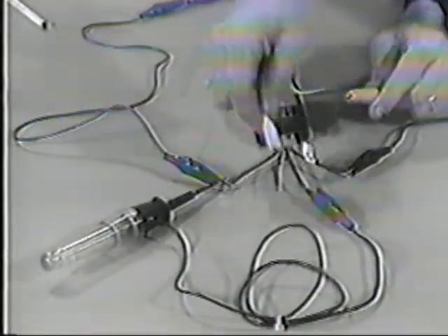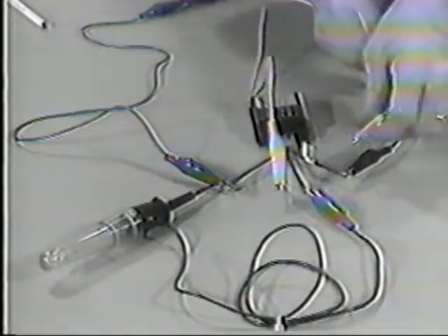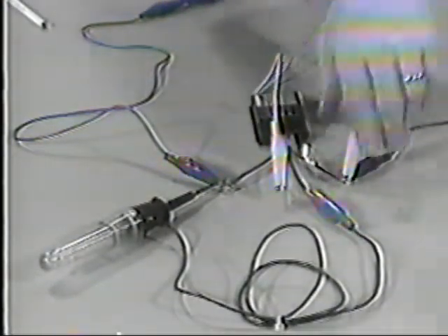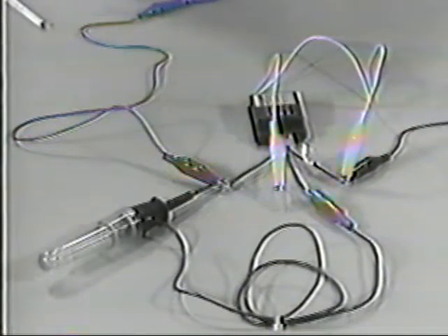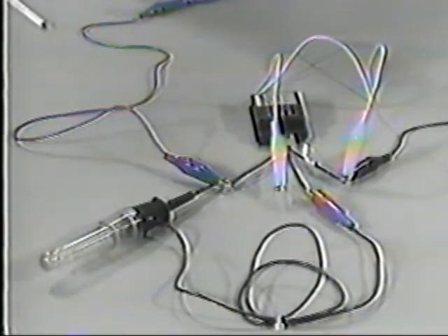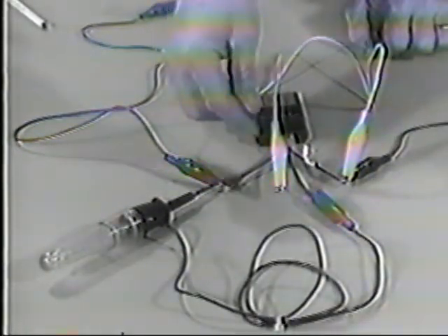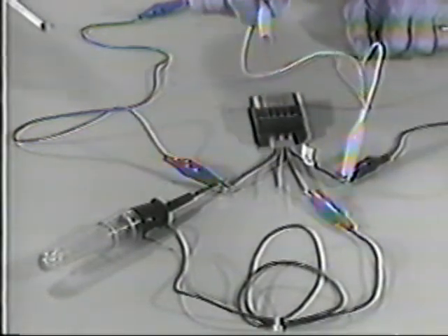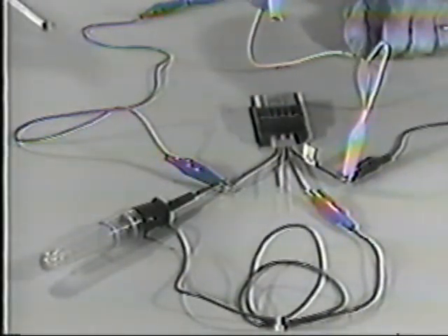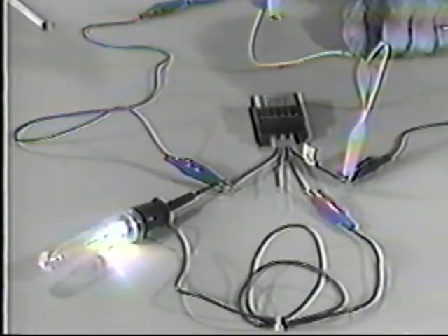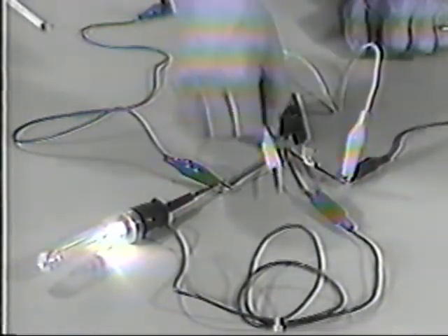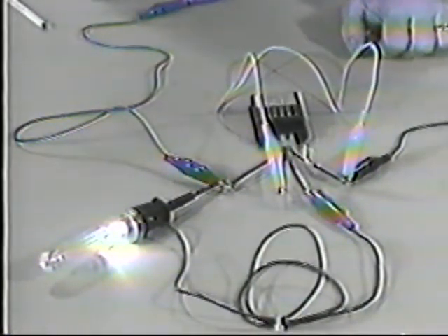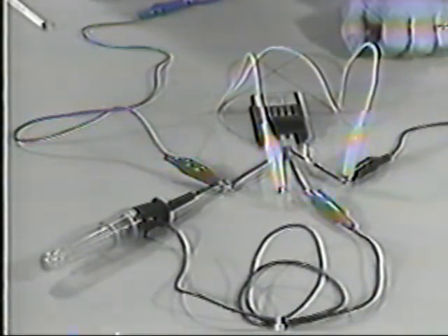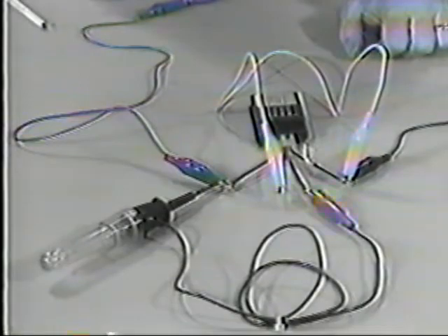Jump the number 2 terminal to ground, which of course is post number 4. When we turn the power on, the module should go through a brief self-test indicated by the test light flashing. Okay. To simulate a low water situation, disconnect the jumper wire from post 2. There'll be a brief delay, what we call a slosh delay. The test light should come on. Reconnect the jumper wire to post 2, simulating that the water has come back, and after a brief delay, the test light should go out. Any module that does not act like this has a problem.